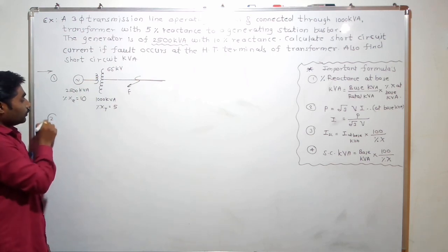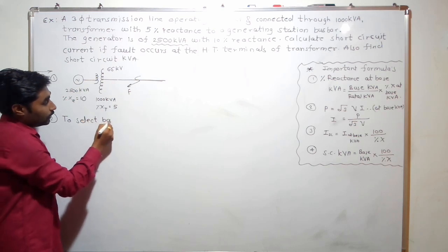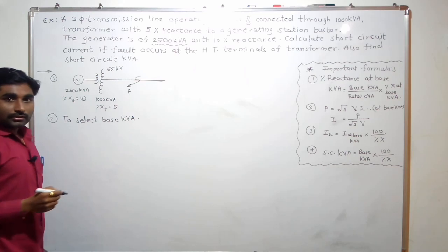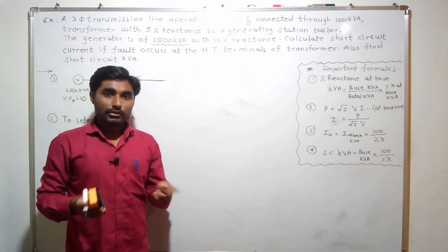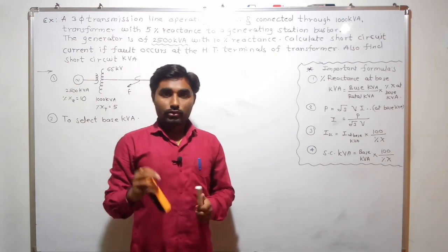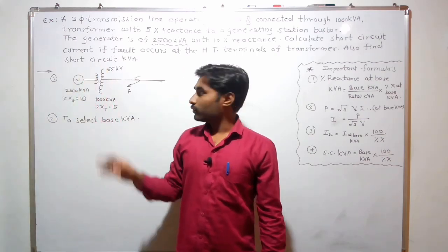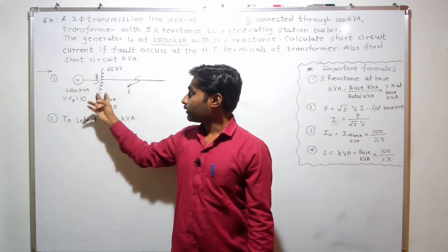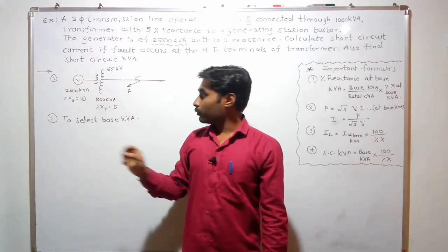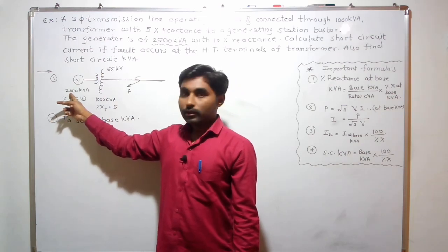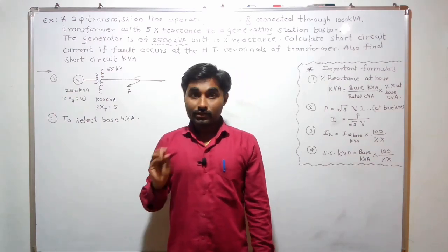The next step, the second step, is to select the base kVA. There are three methods to select the base kVA. First, we can add the kVA ratings of all components in the circuit — generator is 2500 kVA and transformer is 1000 kVA, giving 3500 kVA. Second, we can choose the largest kVA rating of any component, which is 2500 kVA from the generator.